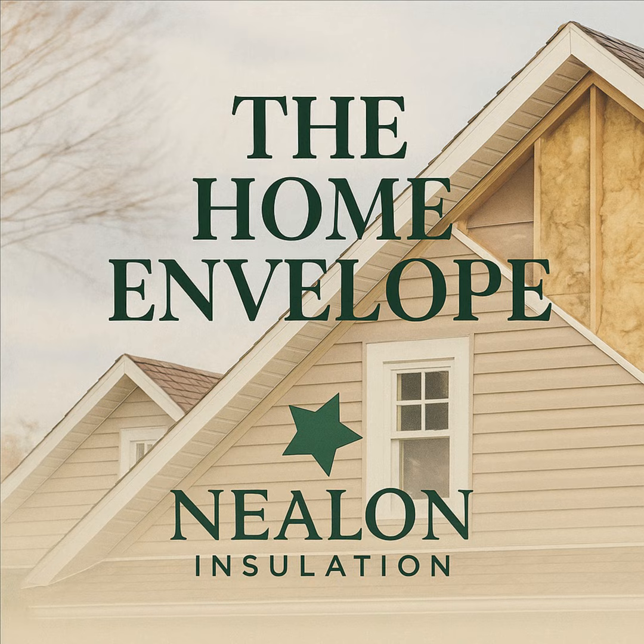But wait, if we pack the edges of the attic with deep insulation to stop those thermal bypasses we talked about, don't we risk suffocating the soffit vents at the eaves? It's actually one of the most common installation failures. I can imagine. Contractors blow in the cellulose and completely bury the soffit vents. To prevent this, installers must use baffles.